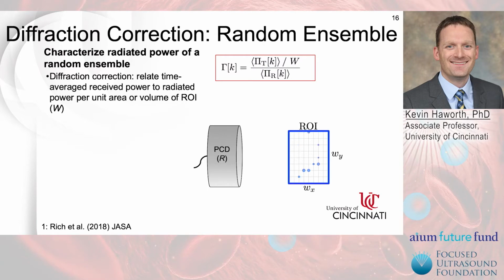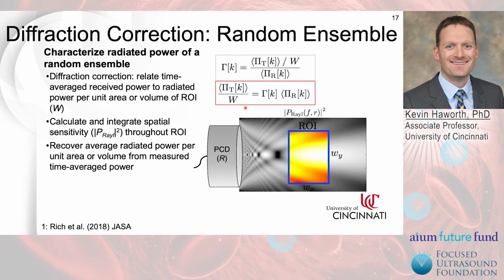Rich et al. proposed that we could potentially deal with this by the inclusion of a diffraction correction factor, which they termed gamma. They defined it as the average total radiated power normalized by the region of interest, which is shown right here as this box, and indicated by W in this equation, divided by the average received power. In this scenario, we measure the average received power, and we can estimate the region of interest based on the focal volume of the therapeutic insonation transducer. This allows us to rewrite our equation as the total radiated power per unit area is a product of the diffraction correction factor and the received power.